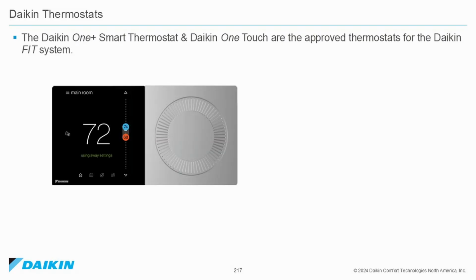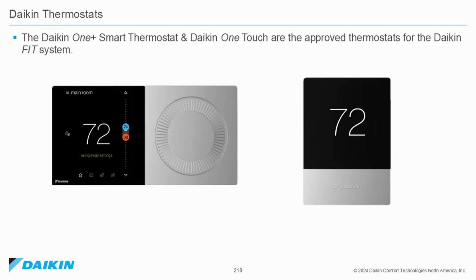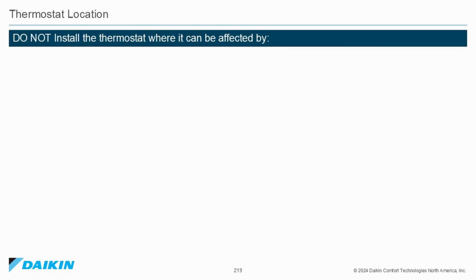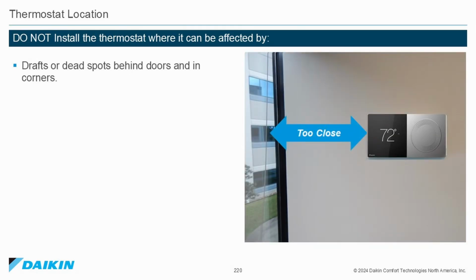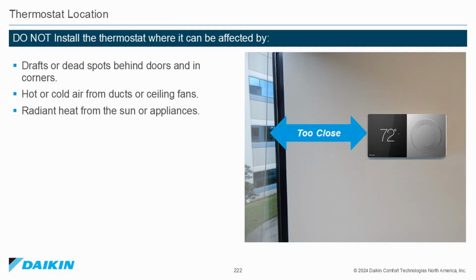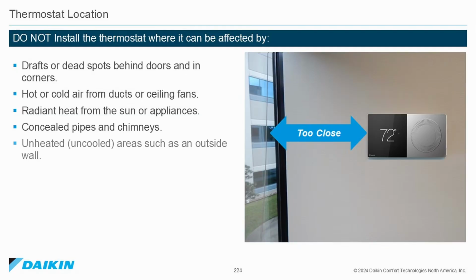Daikin thermostats. The Daikin One+ Smart Thermostat and the Daikin One Touch are the approved thermostats for the Daikin FIT system. Thermostat location. Do not install the thermostat where it can be affected by drafts or dead spots behind doors and corners, hot or cold air from ducts or ceiling fans, radiant heat from the sun or appliances, concealed pipes or chimneys, unheated or uncooled areas such as an outside wall.